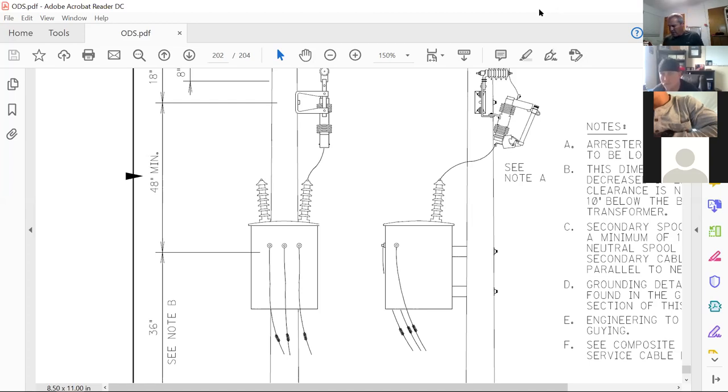So that's why I'm saying don't make the assumption that if I double or triple the size of a transformer, the fuse is going to double or triple also. Okay. Because they have that room for latitude. Let's do the math.